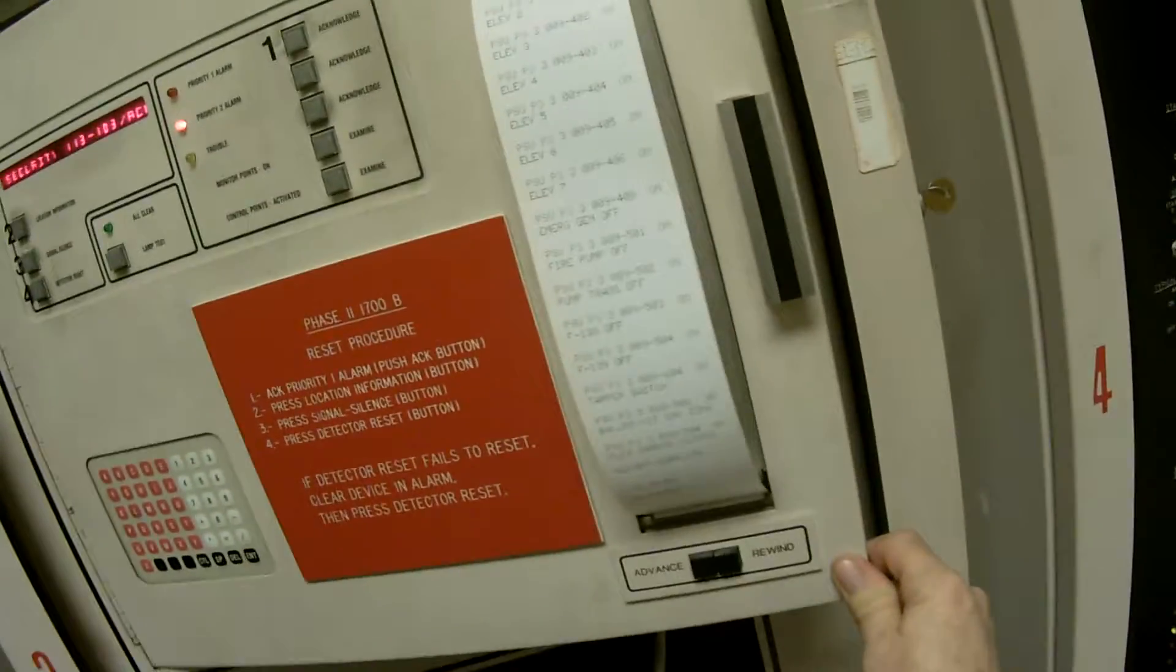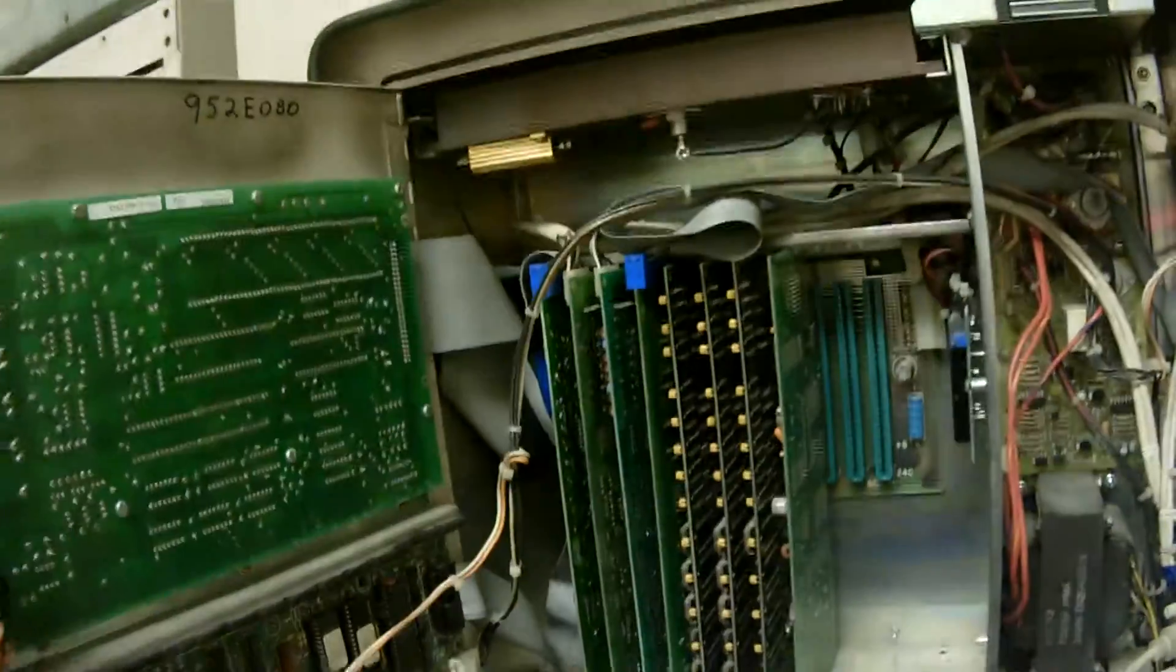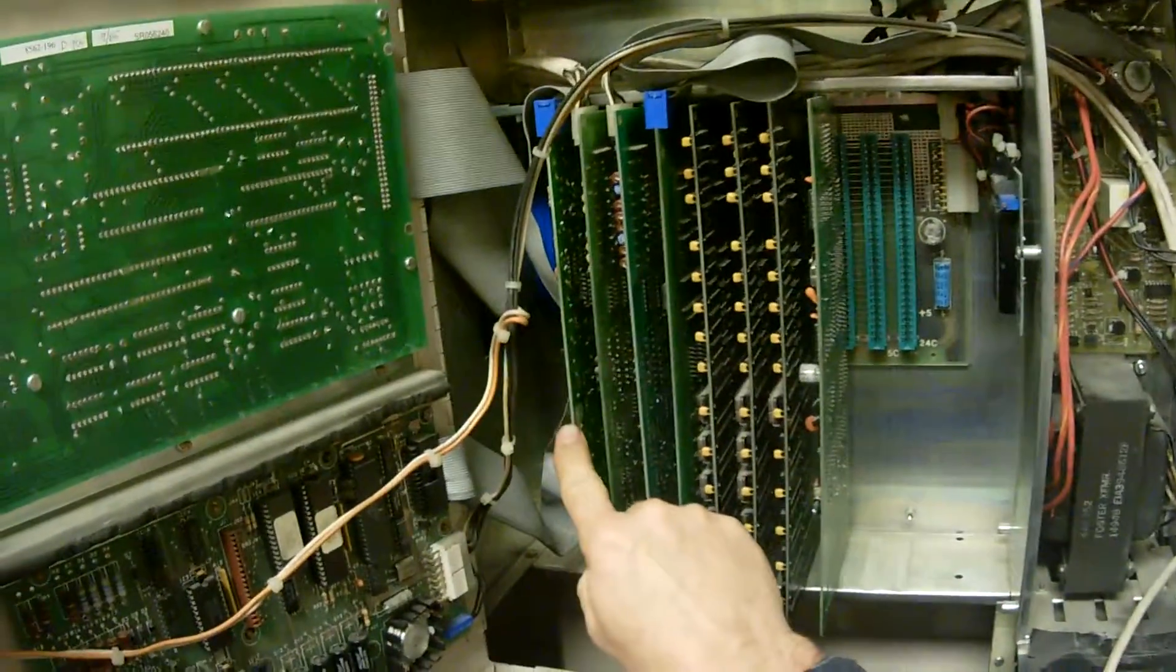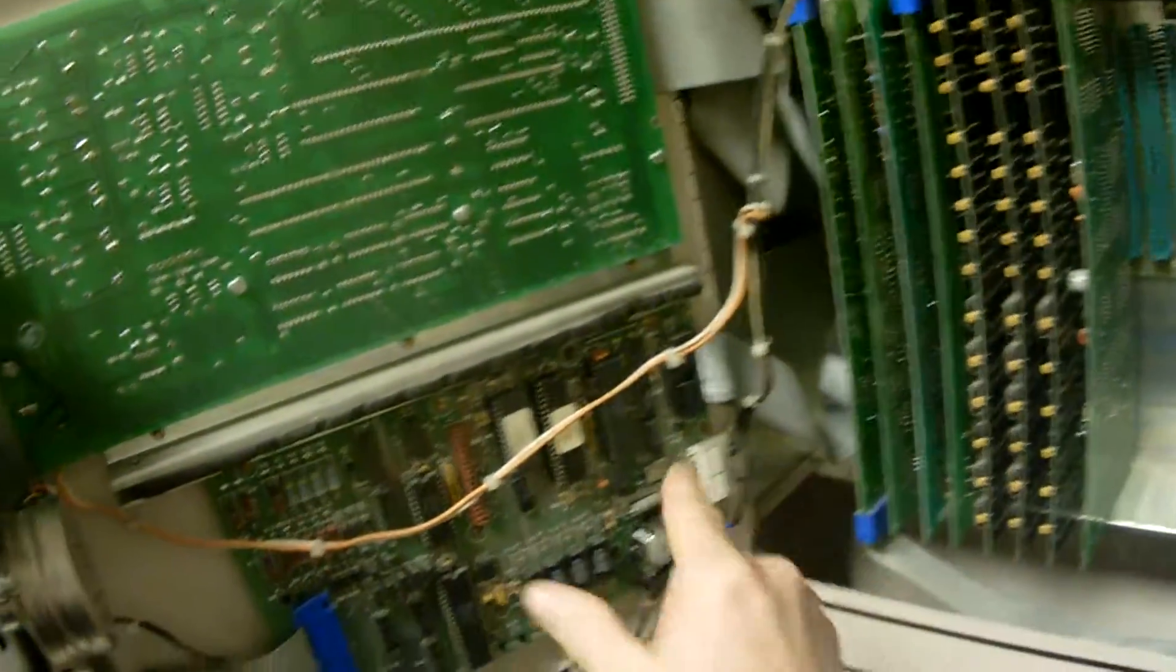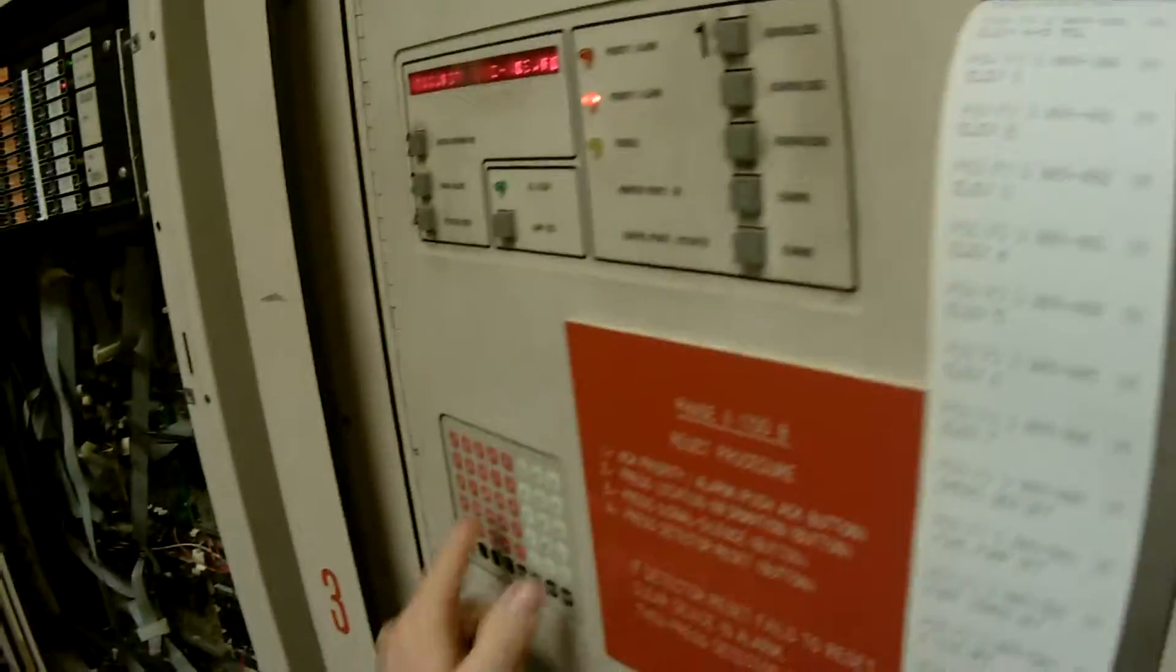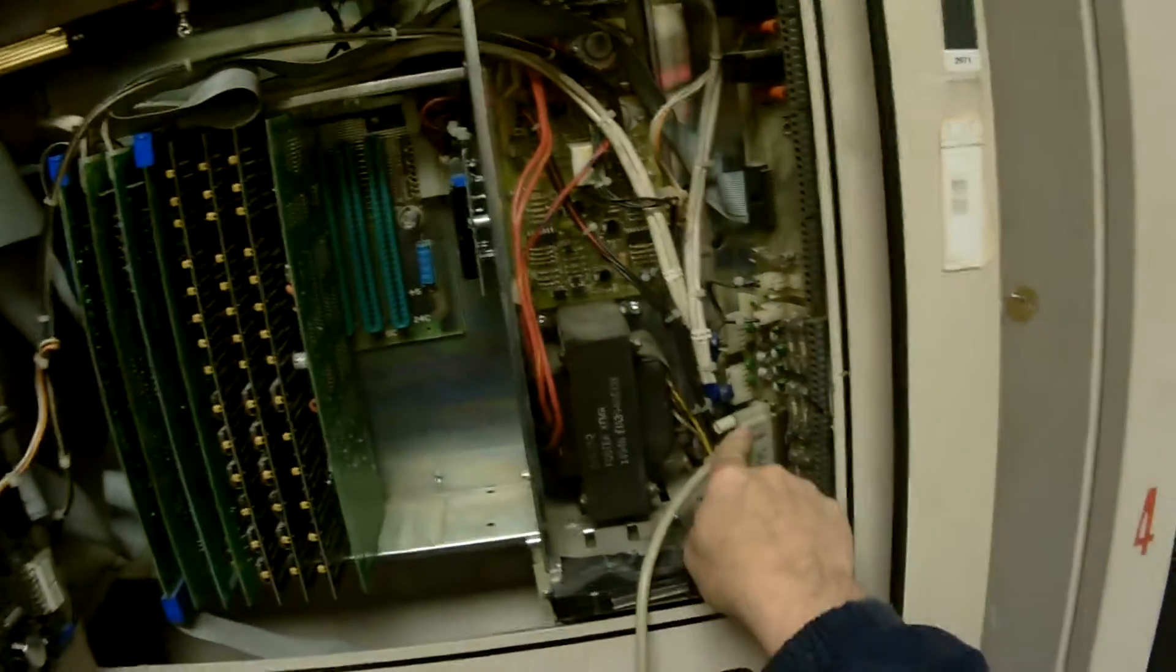Now you might be thinking, well, what about device number one? Well, it's an RS-232 board in the panel here. It has two ports. Port number one goes to our printer board for our local printer and keypad right here, so that handles port number one. And port number two goes to this RS-232.